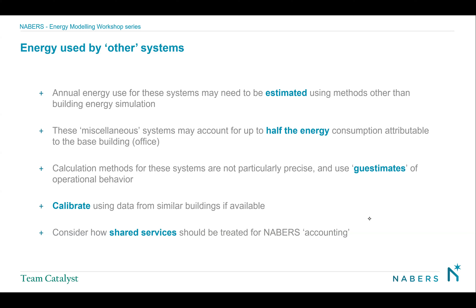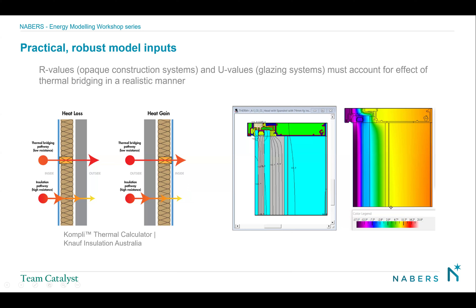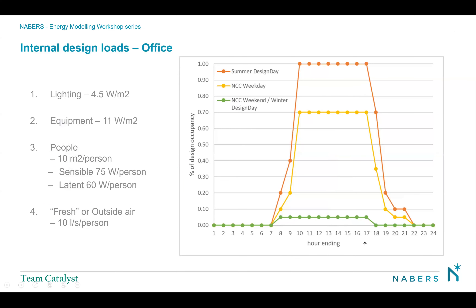Looking at the inputs that go into the model, you start from the building fabric side. You want to use realistic numbers for everything. When you're talking about R values or U values, you do need to think about thermal bridging — that bridging is going to reduce the performance, and you need to account for that in your energy simulation. This is no longer about compliance; this is about what will really come out of the meter.